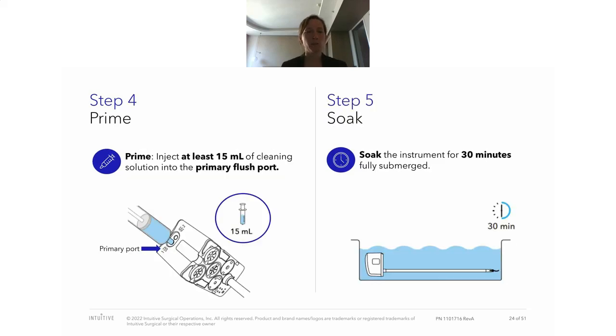Once the solution is prepared, we can start with the priming. And the priming is very similar to what has happened in the OR. It's injecting 15 milliliters of the cleaning solution in the primary flush port. If you remember the primary flush port, that's the one that goes into the shaft and fills the shaft. And then there's a soaking step for 30 minutes where the instrument is fully submerged.